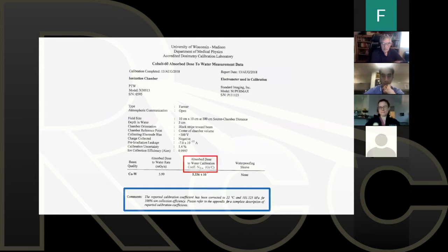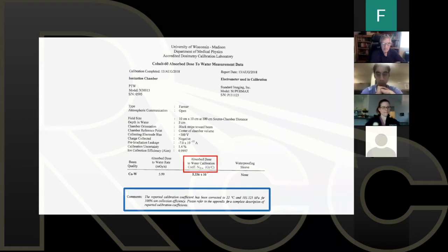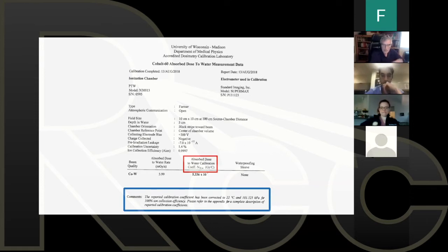This is what my calibration report looks like. And this is from the University of Wisconsin in Madison, Wisconsin, US. It's cobalt-60 absorbed dose to water. I've outlined in red the important number, 5.336 times 10 to the 7th grays per coulomb. That is my NDW. That is the calibration factor for getting me from coulombs, which is measured by my electrometer, and every electrometer in use today is going to be measuring coulombs. How do you get from coulombs to dose to water? You use this NDW. It's a very, very important factor.